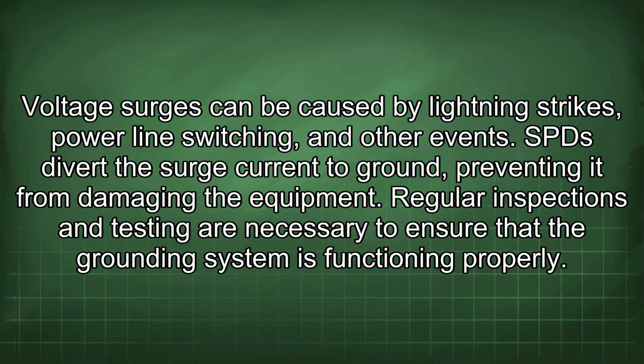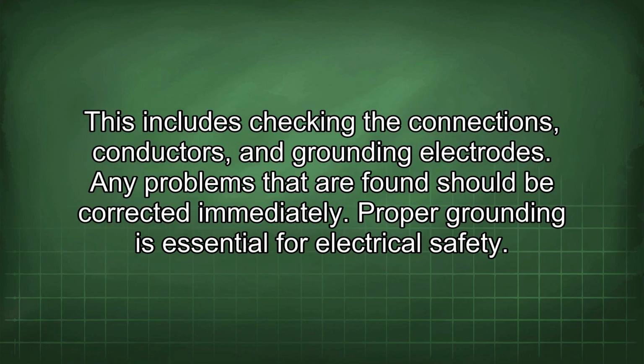Regular inspections and testing are necessary to ensure that the grounding system is functioning properly. This includes checking the connections, conductors, and grounding electrodes. Any problems that are found should be corrected immediately.